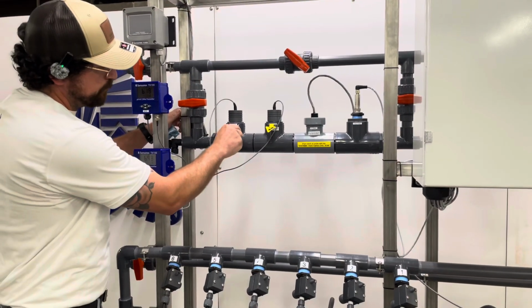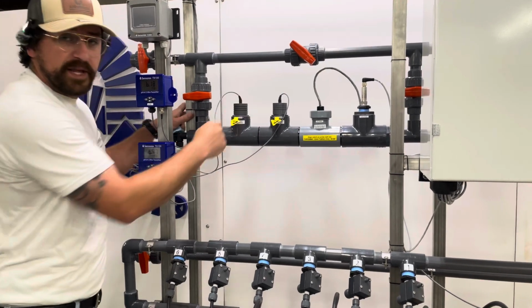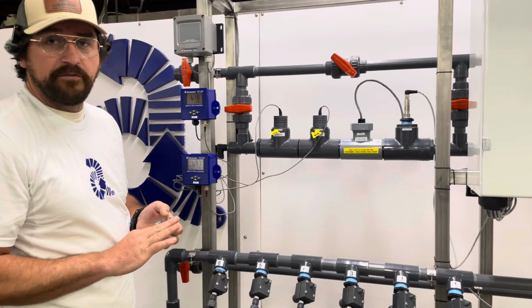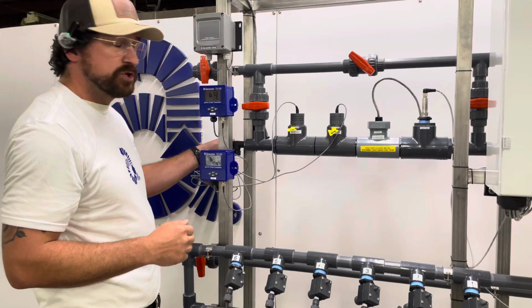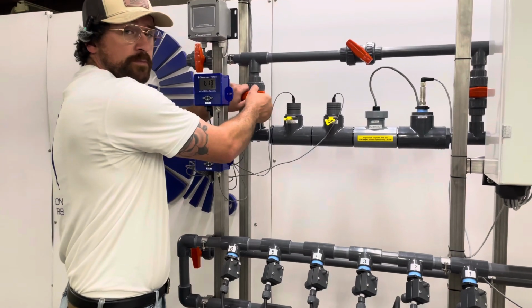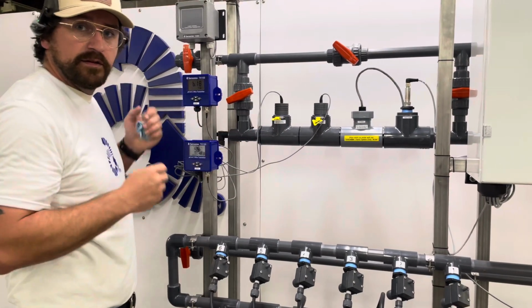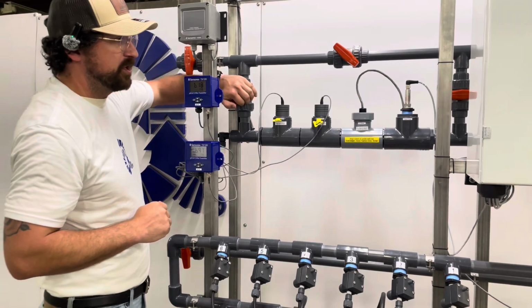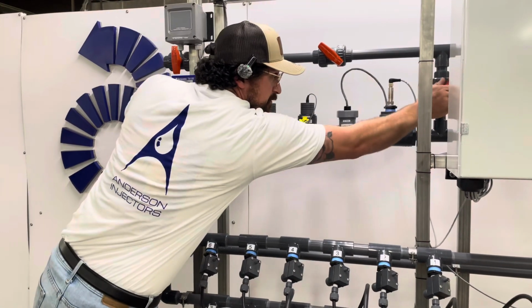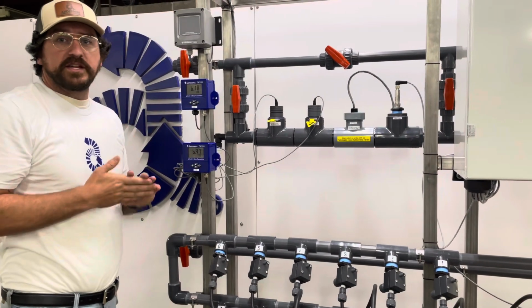Put the U-pin in, and you'll repeat the process for the second probe. After that's finished, you're going to close your drain valve. You're going to crack open your ball valve just a little bit, let the probe loop pressurize, and then you can safely open both of these verticals. And now you're complete.